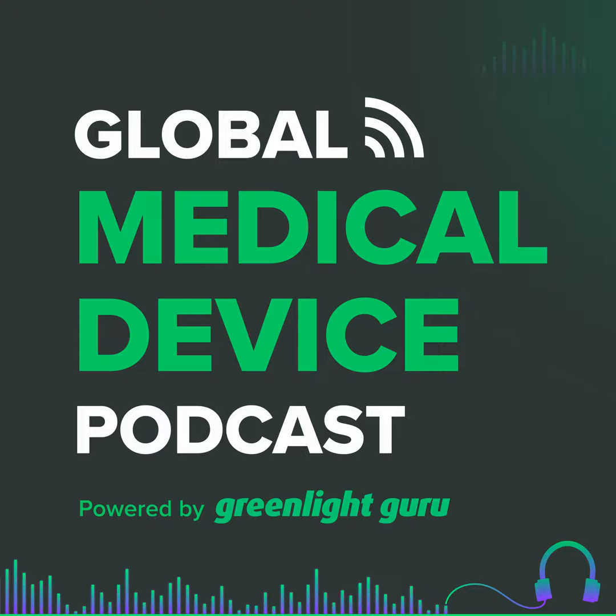Keep in mind, and I personally think this is a weakness in the GCPs, the good clinical practices, IRBs exist at institutions like hospitals and medical schools and so on. They're, for the most part, clinical people and scientific people, not necessarily engineering people. So when it comes to issues like biocompatibility or electrical safety, these are things that are kind of assumed by most clinical people. But an engineer, a good biomedical engineer, I'm sure, I hope, would never make such an assumption, right? And so because you're not dealing with the FDA in this case, you're only dealing with the IRB. The review of the IRB is critical to the safety of the patient.